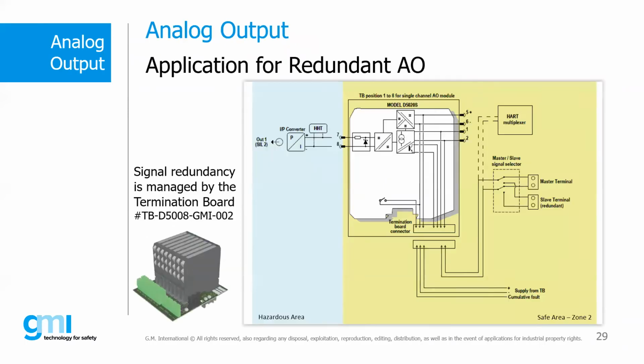Now, let's see how it's possible to manage a redundancy system for analog output type applications. In this specific application, the management of two 4-20 milliamp signals towards the dangerous area is not a simple solution, as the two signals should be mixed or added in some way. GMI has developed a redundancy system through a special termination board, which takes the two signals coming from two analog output cards of two different PLC systems and mixes them through its own process logic.